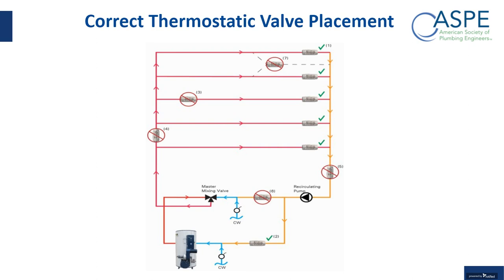So the advantage of a thermostatic balancing valve in this application is it can adjust the flow of the water back to the water heater based on the return temperature, so that you have a better chance of mitigating either temperature creep or temperature droop. So it's another great application. It's not a traditional balancing application, but it's another great application for a thermostatic balancing valve in a domestic hot water system.